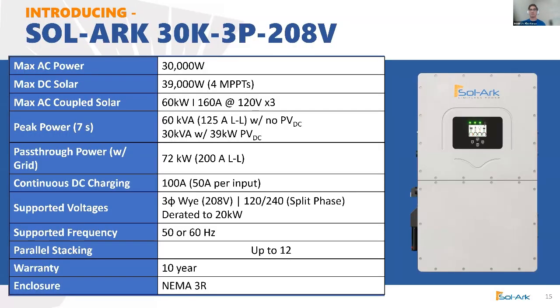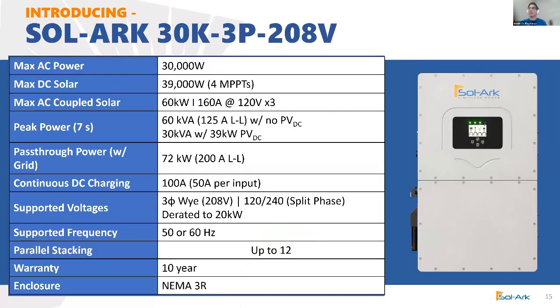The grid pass-through is going to be 72 kilowatts, the 200 amp relay that we mentioned. And it does have 2 separate battery inputs for up to 100 amps. It will work with 3-phase Y 208 volts, or you can change it to a 120/240 split phase. However, it will be derated down to 20 kilowatts. That's not good. And so you can parallel up to 12 of these units, and with a 10-year warranty, and you can install it anywhere you want as long as the screen is not getting hit directly by the sun. We do have a NEMA 3R rating.